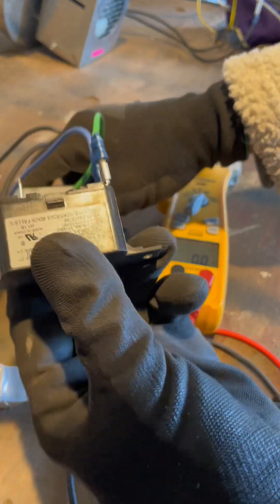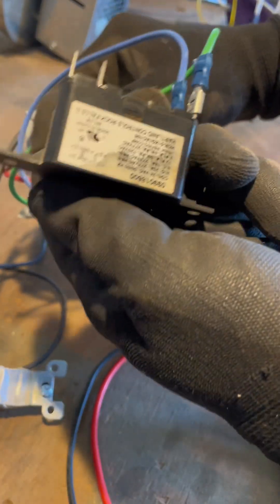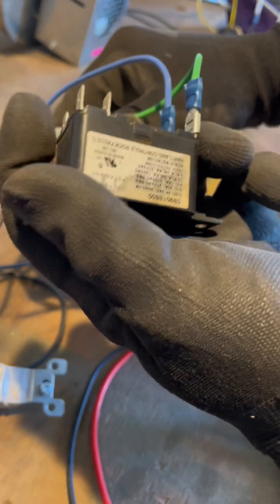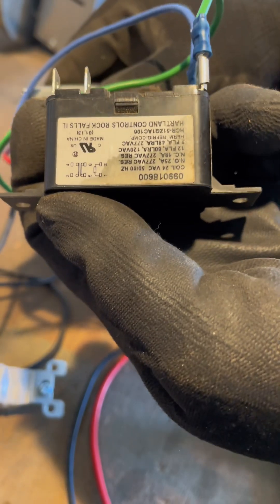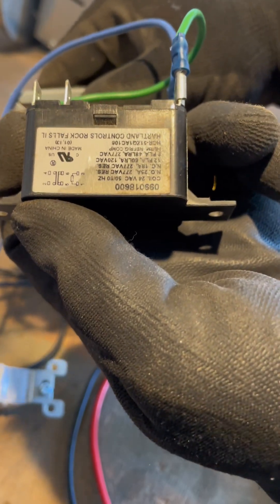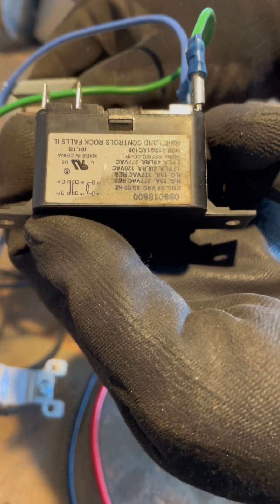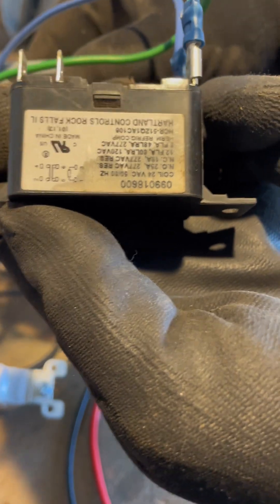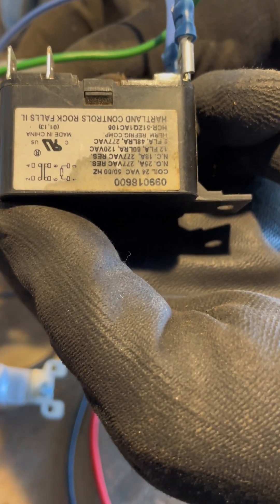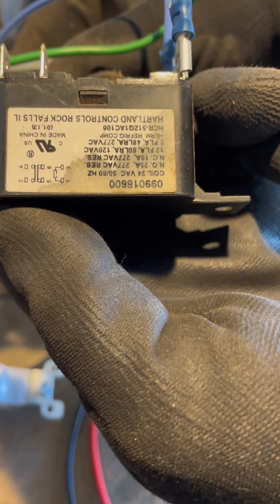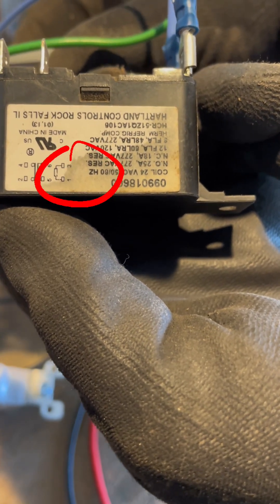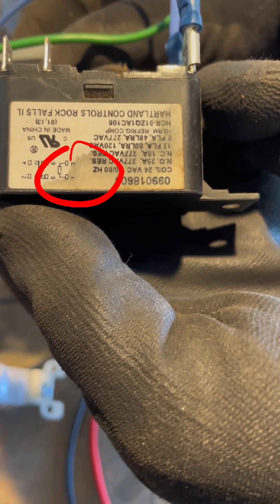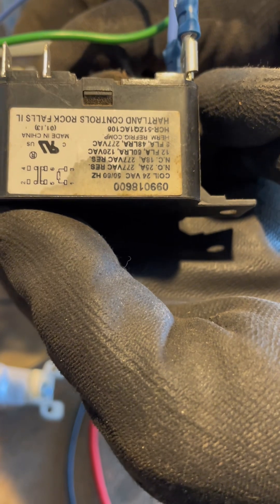So first up, roadmaps. I know everybody's scared of them, but take a look at this one. It's a real easy roadmap on this relay. I just found this relay in the shop and I wanted to test it myself to see if it was good or bad. So here we see between pins one and three, that is our coil, that's our 24 volts being fed, that turns this thing on and off, opens and closes this relay.